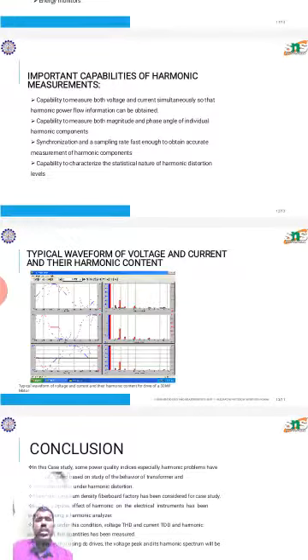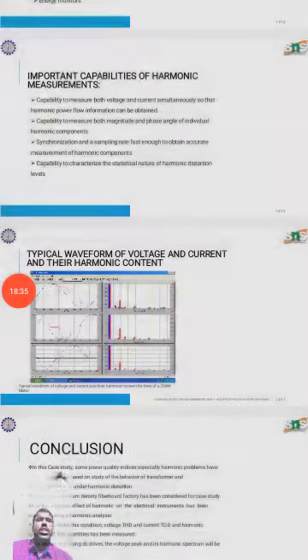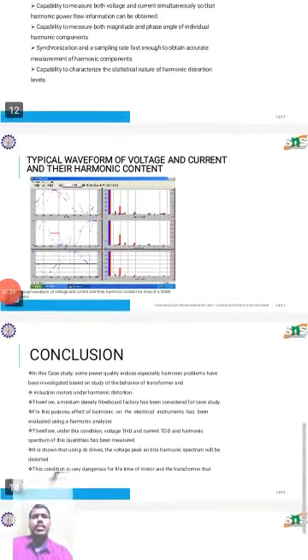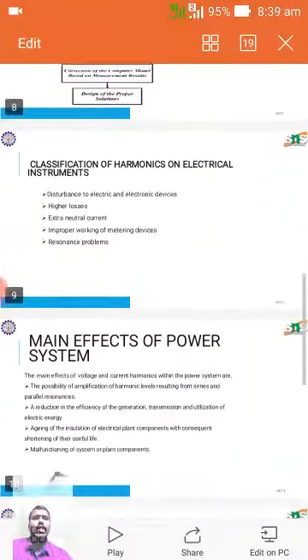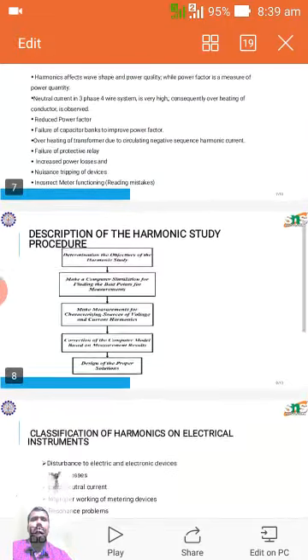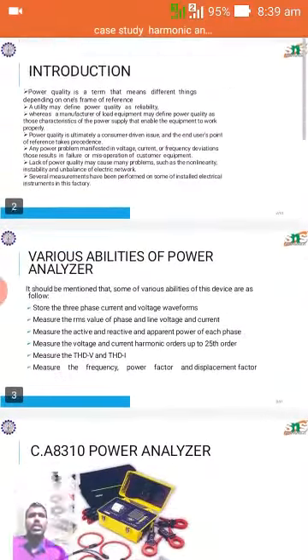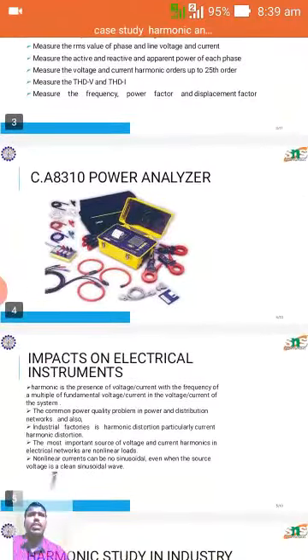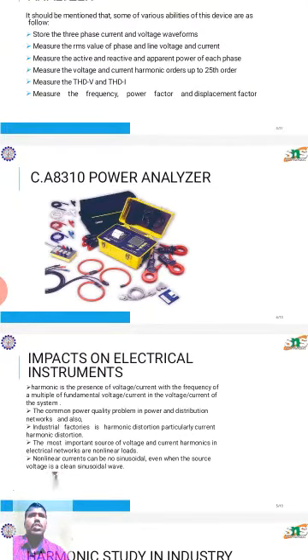This transformer supplies the drives. The phase voltages, the THD of current, TDD, and their harmonic spectra were measured. Finally, this is also the procedure for the harmonics and power supplies of these current distortions.